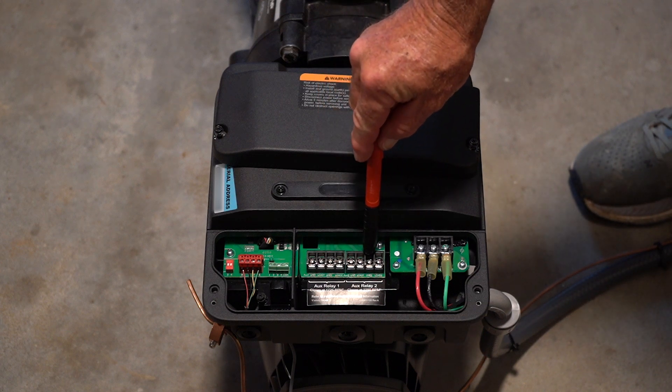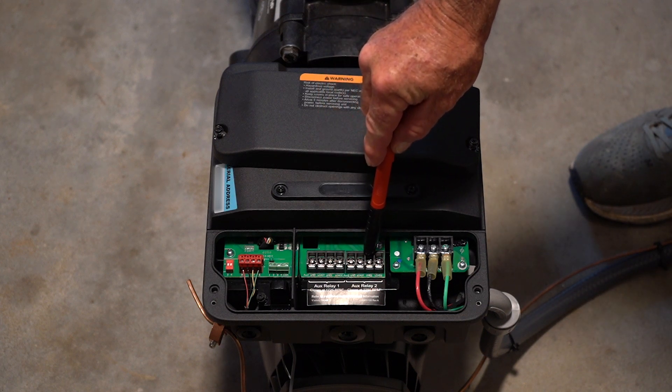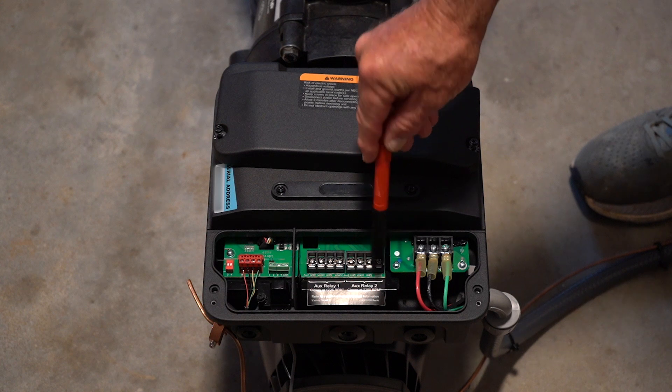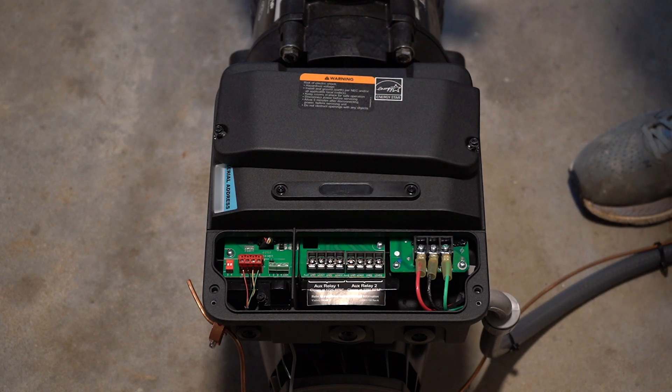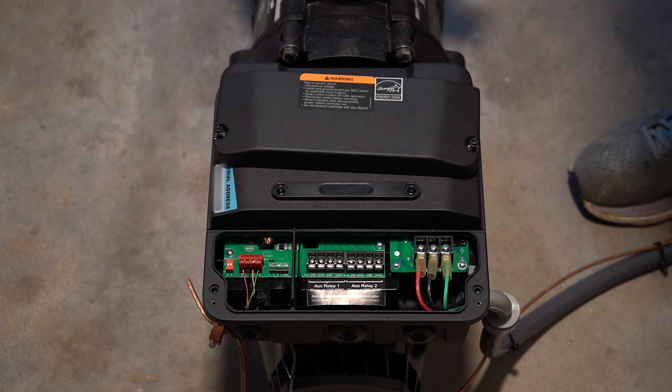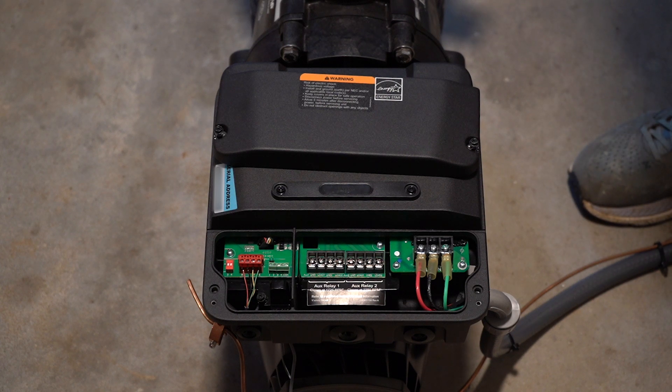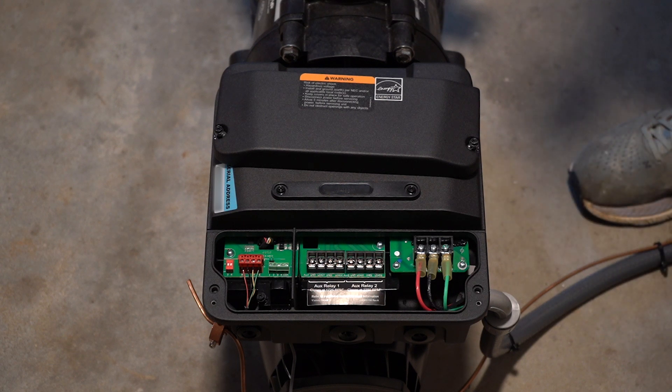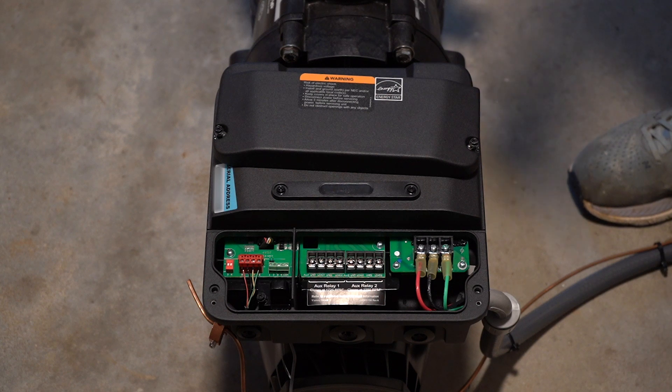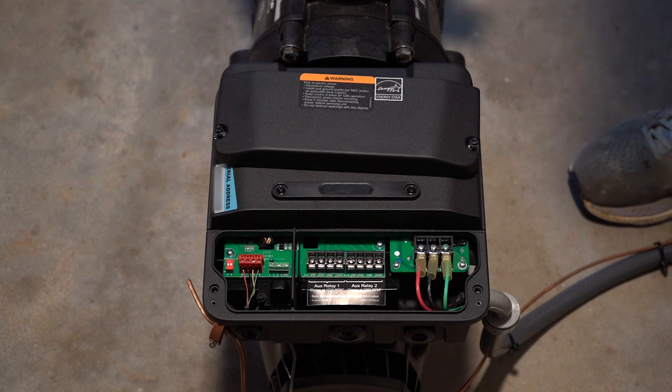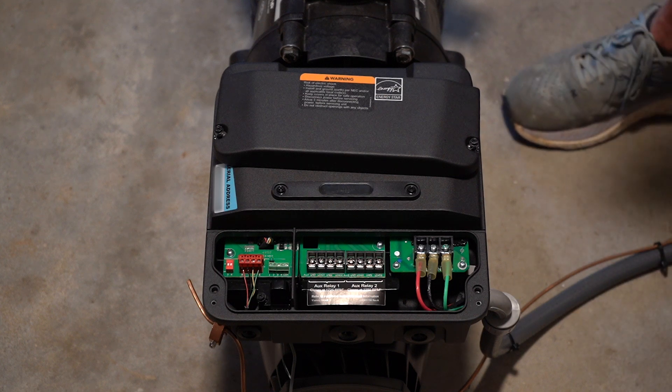Now relay number two engages at 2250 RPMs. Typically that would be used to turn on your heater because if your flow is too low through the heater, you could actually damage it and it'll cause things to trip out and cause problems. So that is the purpose of those two relays. They are coming out with a version that does not have those relays and that'll be a little bit less expensive than this version.